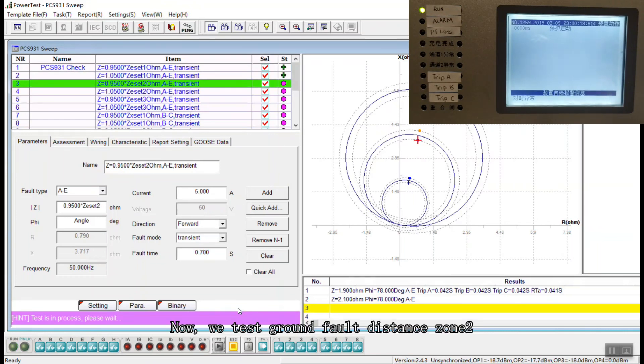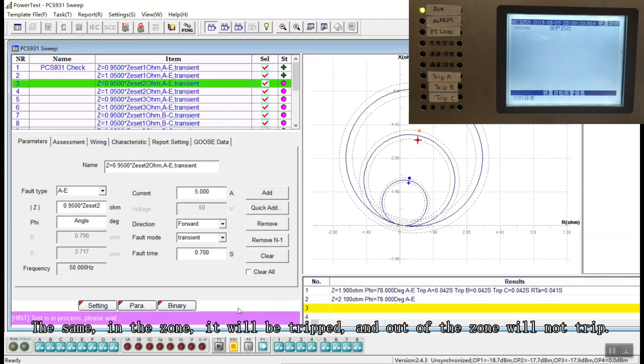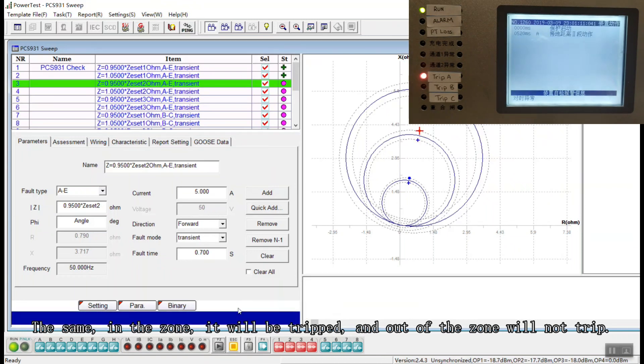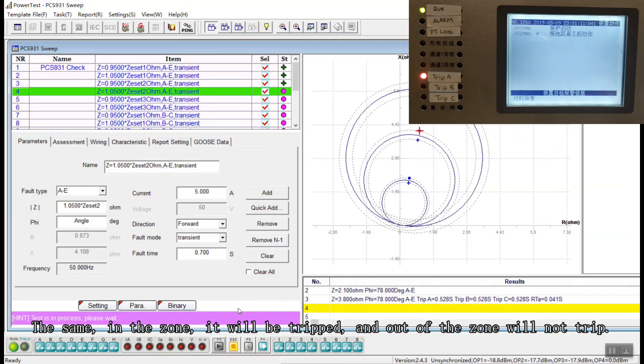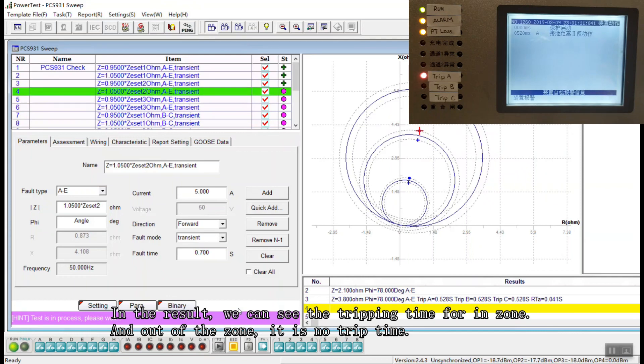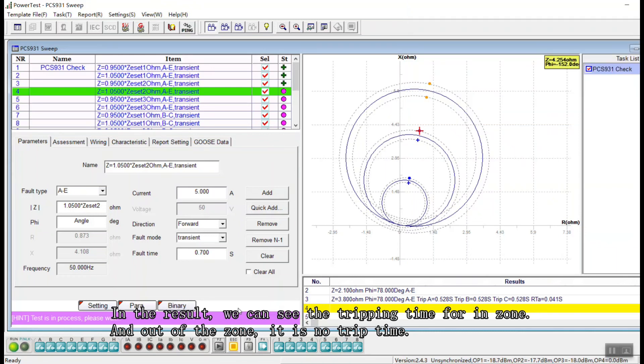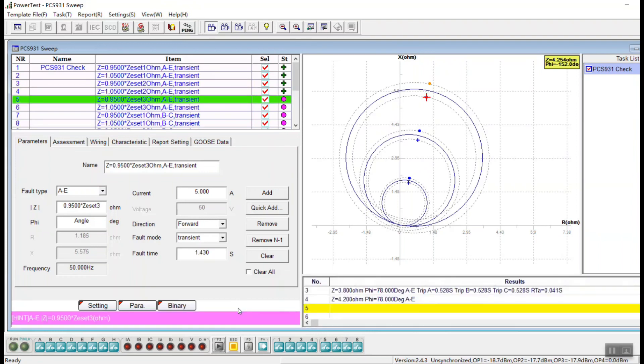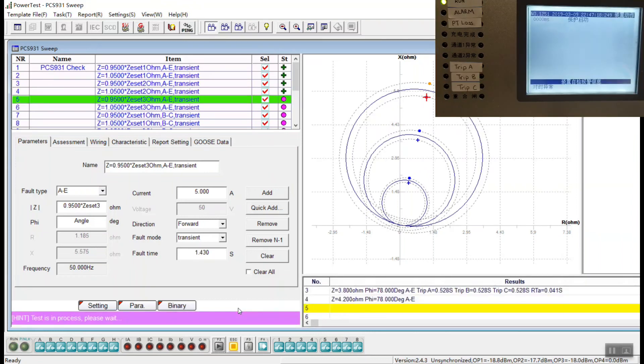Now we are testing the ground distance element zone 2. During faults in the inner zone, the relay will trip. Out of the zone, the relay will not trip. In the results we can see the tripping time in the inner zone, and in the out-of-zone, the relay is not tripped, so there is no trip time recorded.